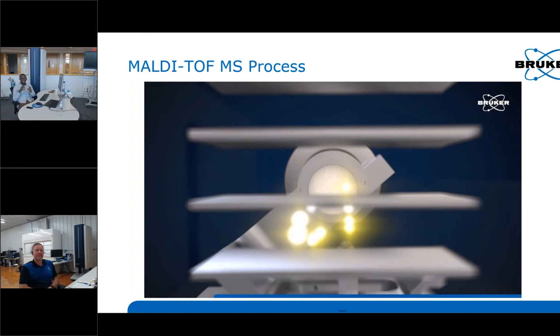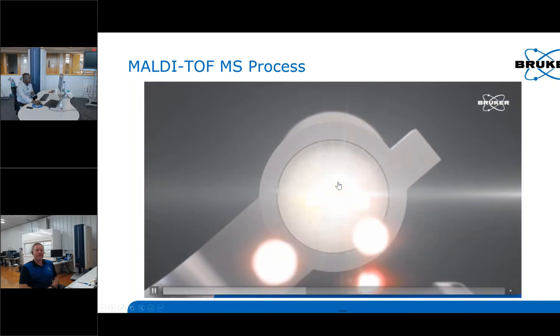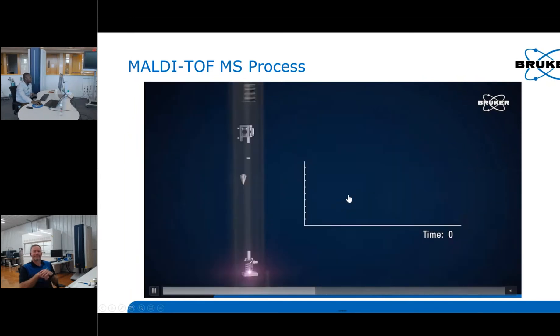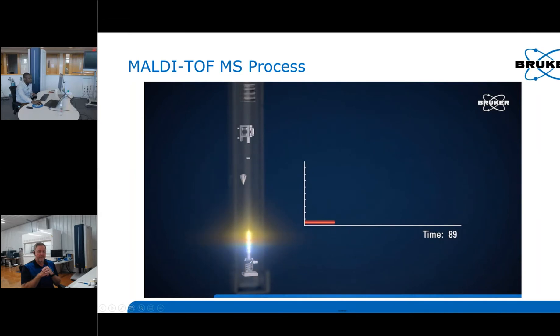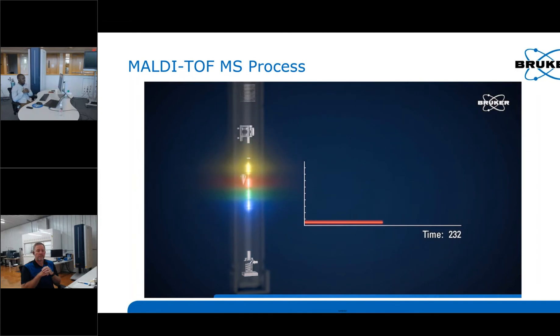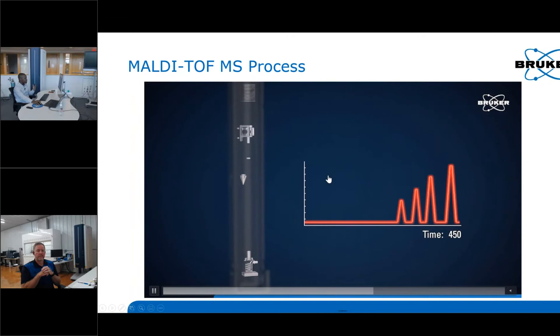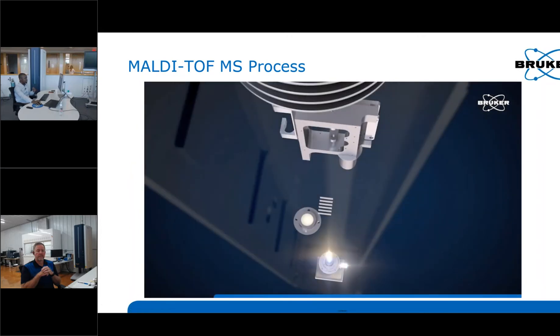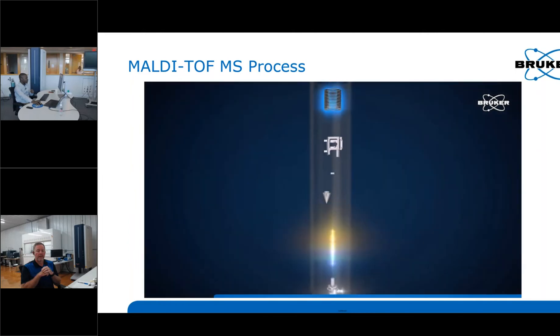The only difference is the masses of the ions that have been formed, which results in different velocities or speeds. In linear mode, the ions reach the detector in just a few nanoseconds after the ionization step. Higher mass molecules arrive later than lighter ones, and flight time measurements are used directly to determine the mass of those ions, which is then turned into a mass spectrum you can read and interpret.